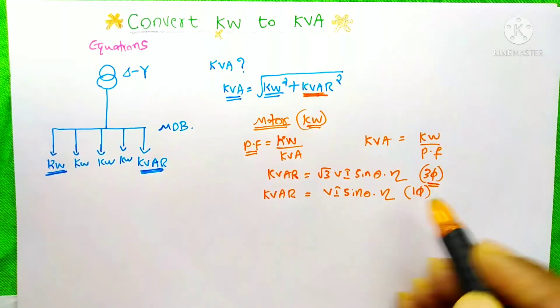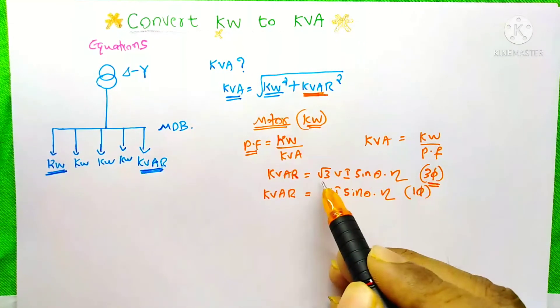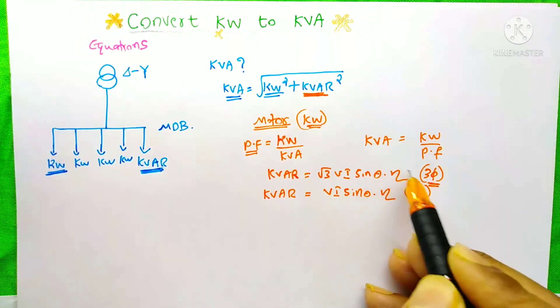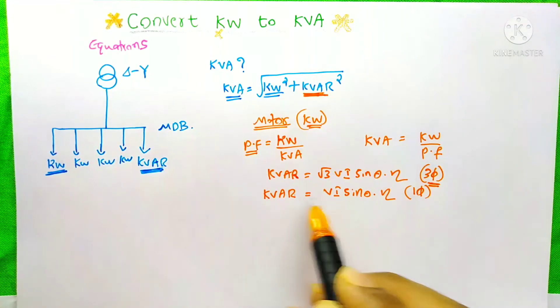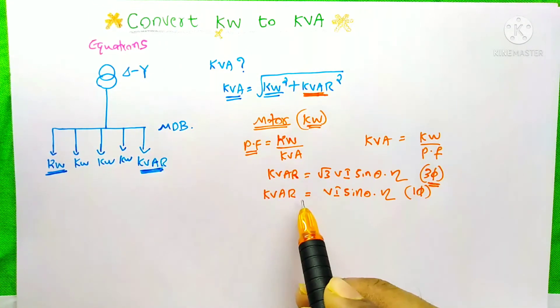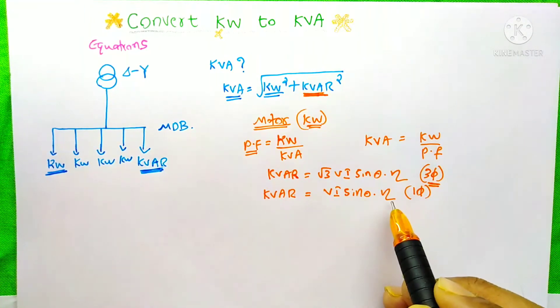For the three phase, we can find this kVAR by using this equation: root 3 V I sine theta times efficiency. And for the single phase, the equation is kVAR equals V I sine theta times efficiency.